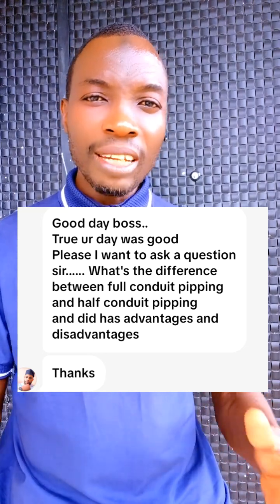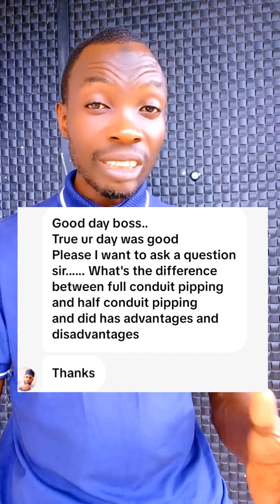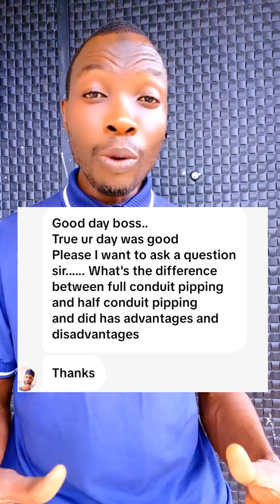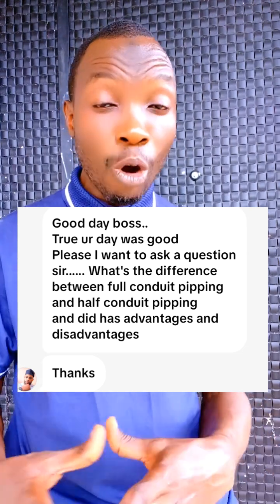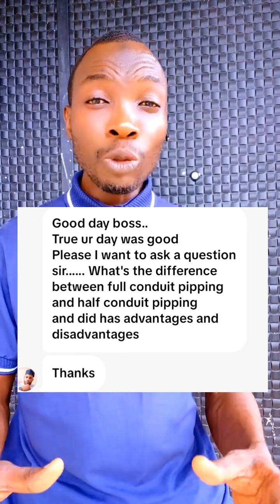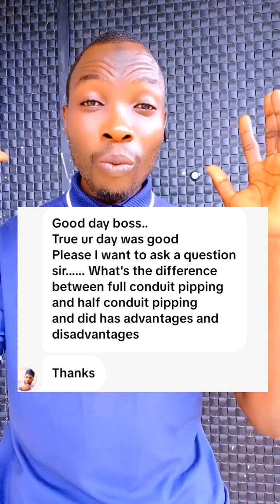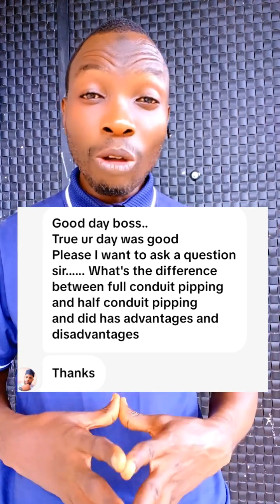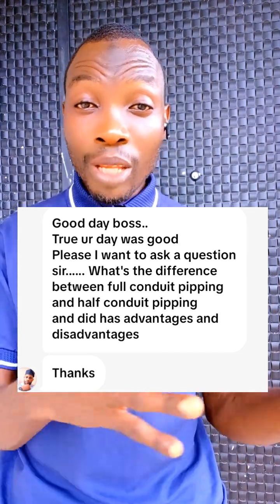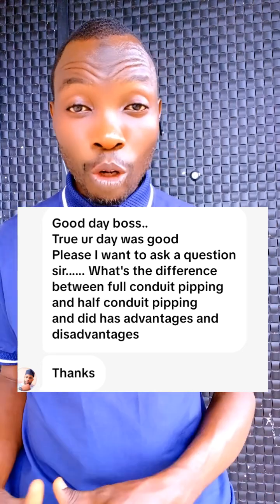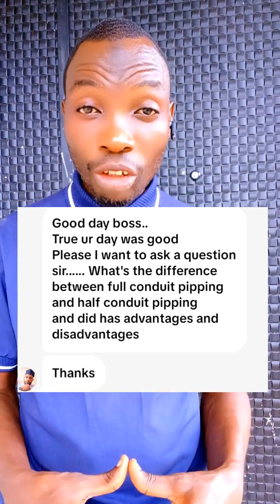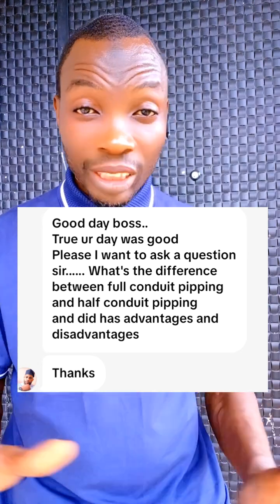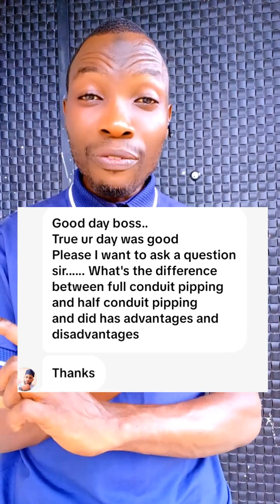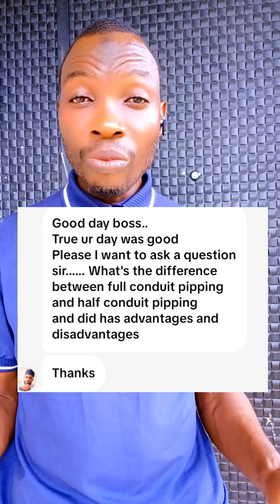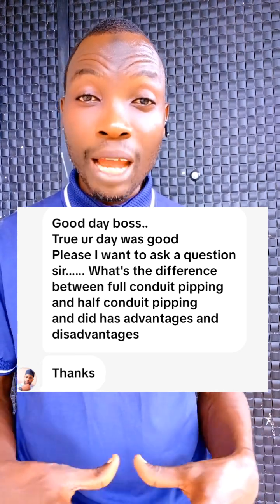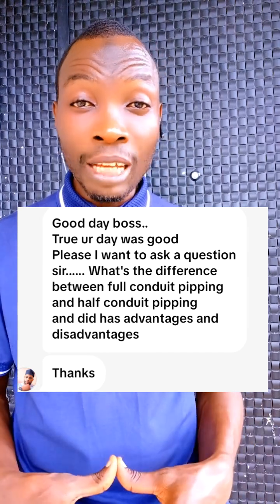We later discovered that in the roof, cables are not concealed in pipes. Cables are just run on the roof, which is half conduit. Virtually all the cables were naked. That is, we did not even see cables there, because a cable is the combination of the insulation and the conductor, but the moment there is no insulation again, it's only conductor that was there. So everything was left naked, only conductors. In fact, thank God we isolated the supply before we started troubleshooting.